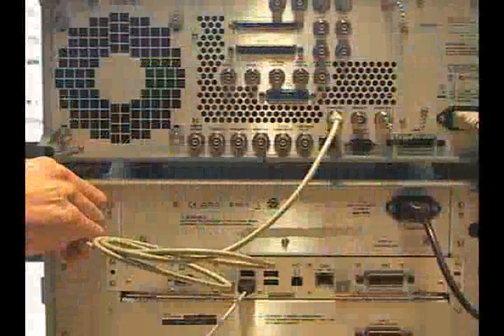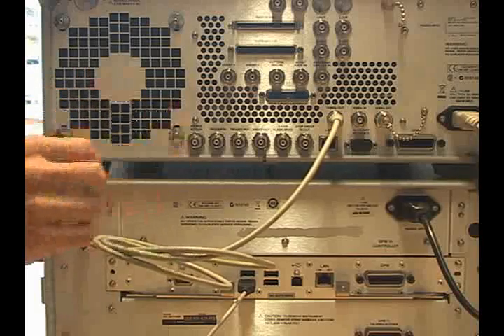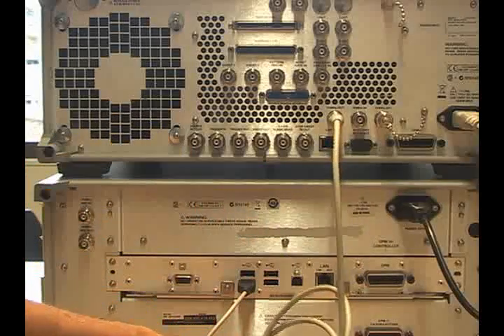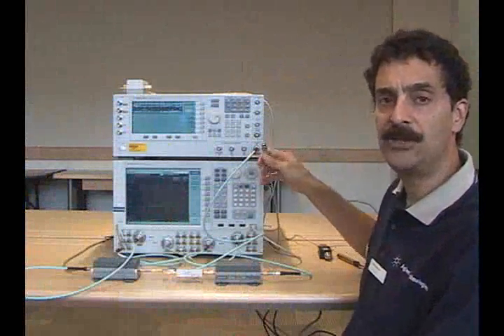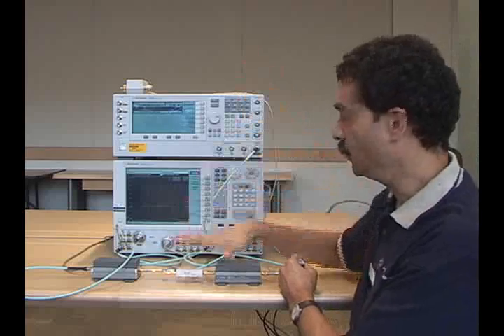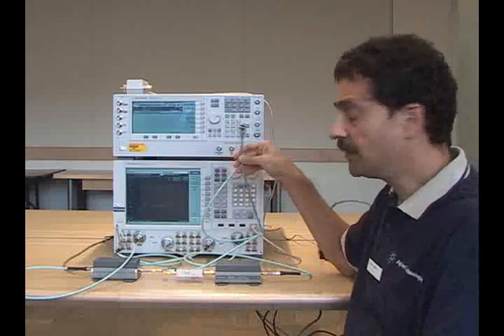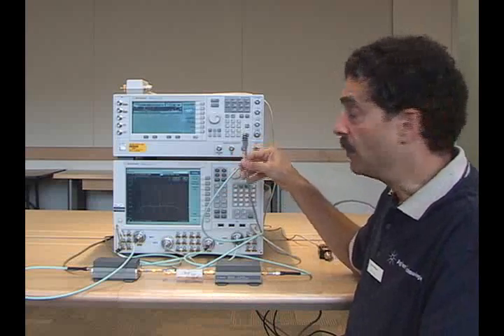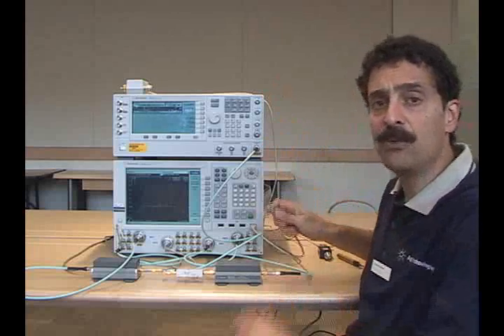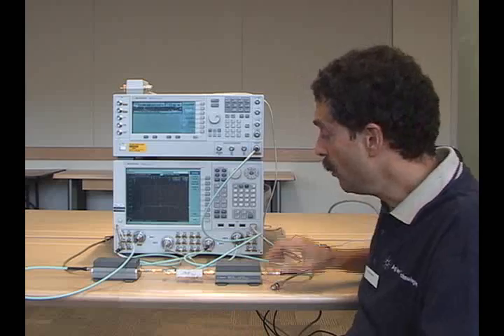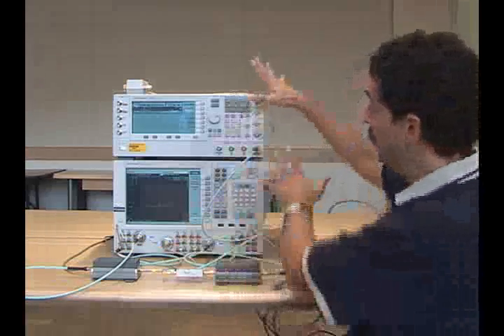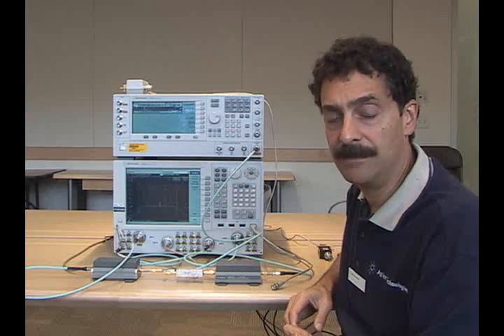Now for this step of the demo where we want a fully embedded local oscillator with no connection, I'm simply going to disconnect the 10 megahertz time base here between the two instruments. So now our PSG is still providing a local oscillator signal to our DUT representing an embedded LO. But now we've disconnected the 10 megahertz time base. So there's no connection now at all between the PSG and the PNAX. And this represents really a fully embedded LO application, where the oscillator that's inside of our DUT being simulated here, has no connection at all to the measurement system.